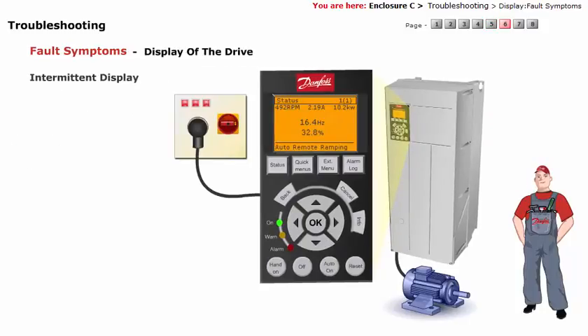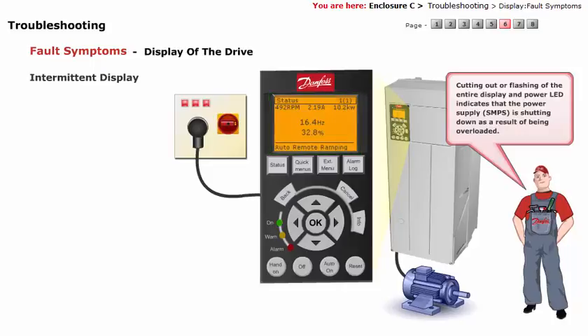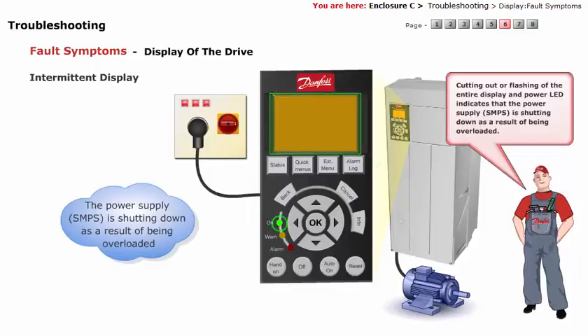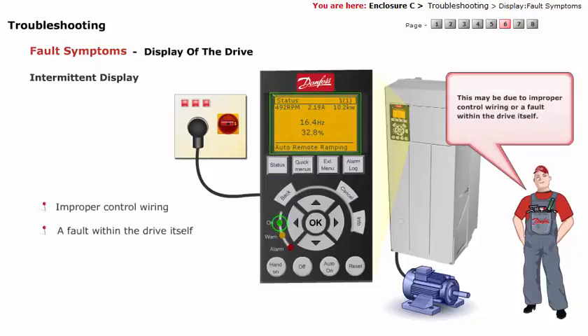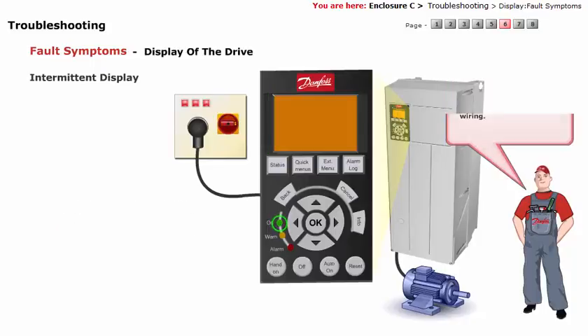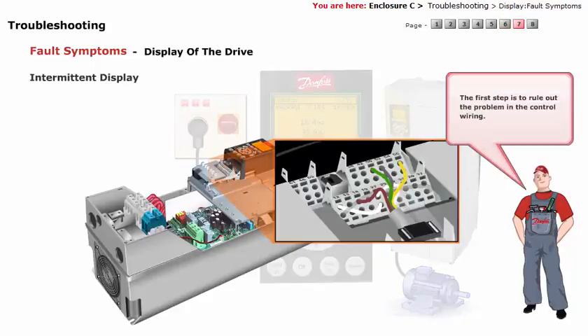Intermittent display: cutting out or flashing of the entire display and power LED indicates that the power supply SMPS is shutting down as a result of being overloaded. This may be due to improper control wiring or a fault within the drive itself.